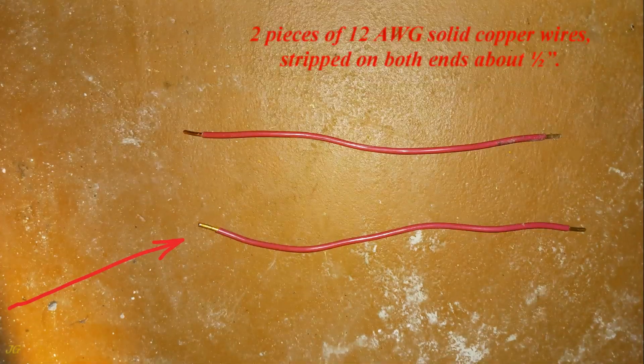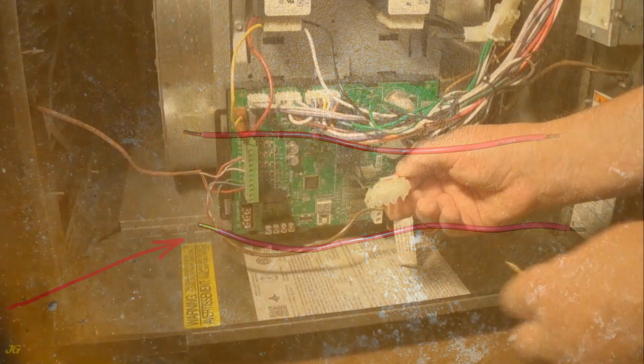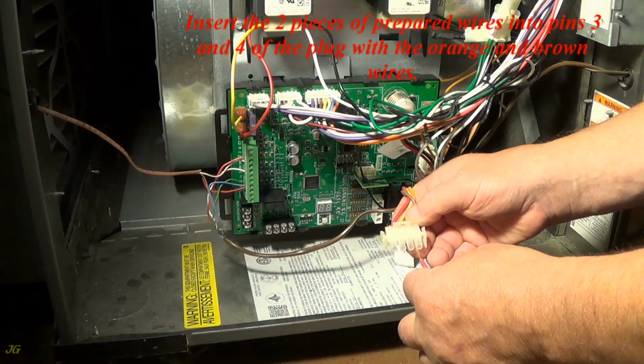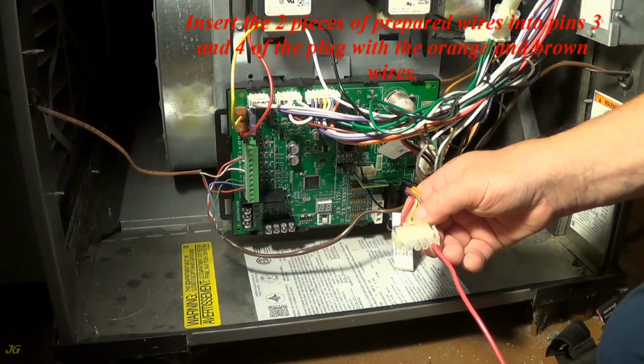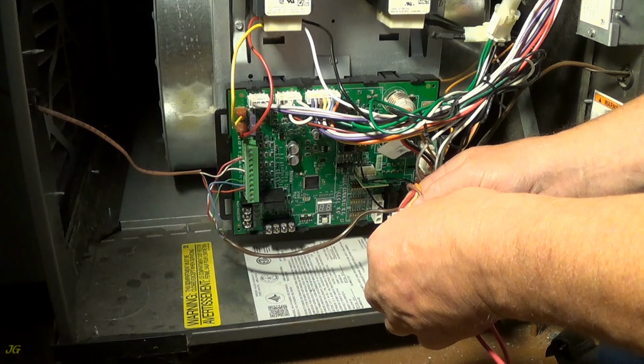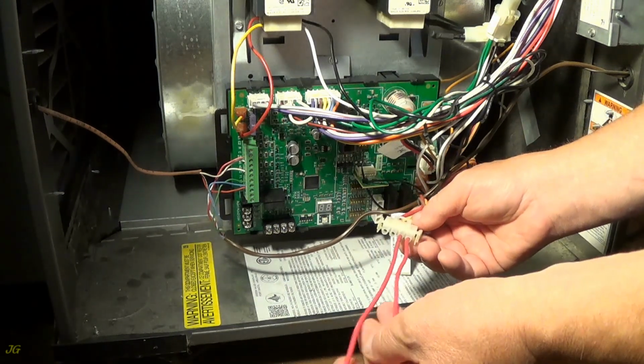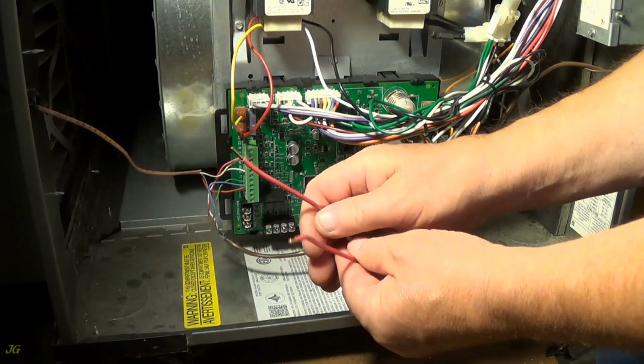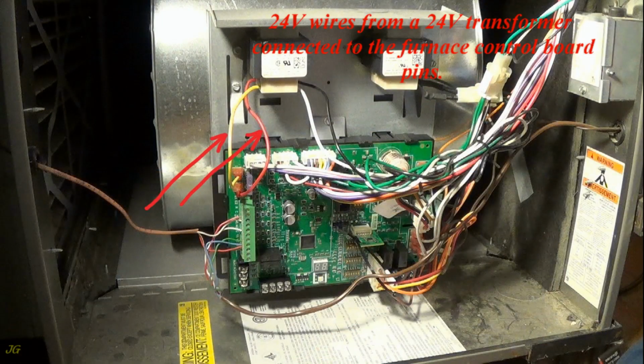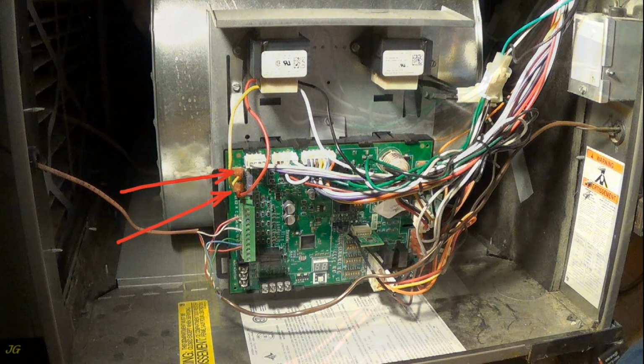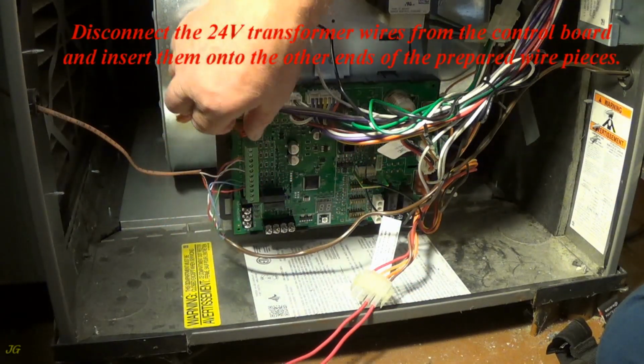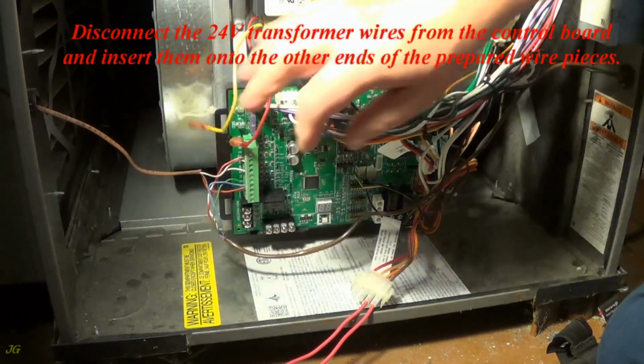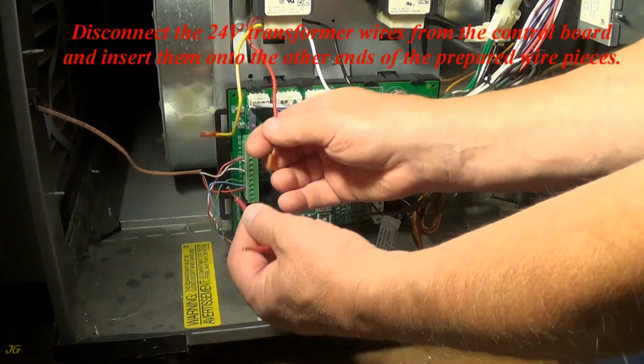2 pieces of 12-gauge solid copper wires, stripped on both ends about 1/2 inch. Insert the 2 pieces of prepared wires into pins 3 and 4 of the plug with the orange and brown wires. 24 volts wires from a 24 volts transformer connected to the furnace control board pins. Disconnect the 24 volts transformer wires from the control board and insert them onto the other ends of the prepared wire pieces.